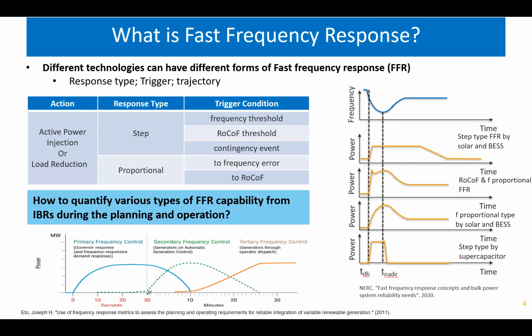It can come from different types of generation units, like PV, wind, solar, even HVDC and load. And speaking of the response type, it could be a step change. It could be proportional to the frequency or frequency deviation. It can be triggered by different conditions. So the question is how to quantify the FFR. It can break down into 2 layers. First, from the control perspective, we think we should quantify, or what we call characterize, the FFR. Second, from the system perspective, we might be able to quantify the FFR performance. So there are 2 different questions here.